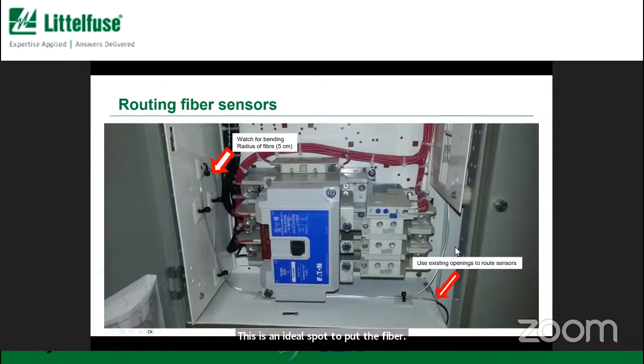Another way that you can use the fiber is if you have a panel that has a lot of equipment, it's very dense, and there's a lot of locations where you want to be able to see an arc. Here on this breaker, there's terminals on the left side and terminals on the right side, so you want to be able to see those. A single sensor does not really have great line of sight to both sides, but here a fiber can come up, be looped around, and come back up along these terminals and then up to the next cubicle.